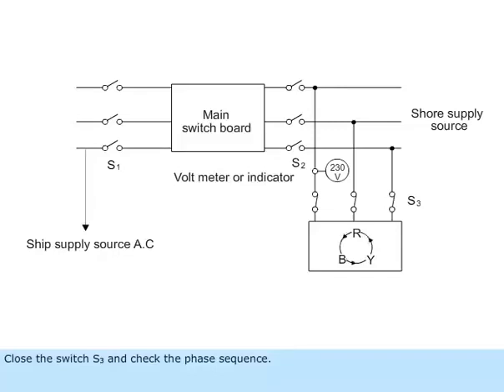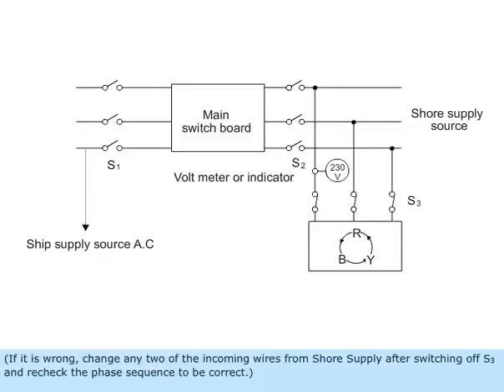Close the switch S3 and check the phase sequence. If it is wrong, change any two of the incoming wires from the shore supply after switching off S3 and recheck the phase sequence to be correct.